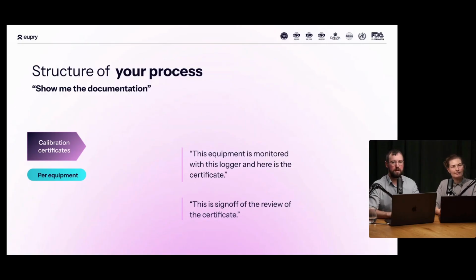We got a question here: if we calibrate the high point at 10 degrees, the materials inside the unit are exposed to temperature out of operating range, is that okay? No, it is not okay. But for excursions specifically, I have yet to see someone storing something in a fridge that did not from time to time experience excursions. The point is, if your target range is 2 to 8 degrees and you have an excursion up to 10 degrees, or sometimes higher, you'd also need to extend your calibration range. You need to show with confidence that the excursion was not more than 10 degrees, and how can you do that if you haven't calibrated it? It's never okay to expose it to more, but when you do have a temperature excursion, you can calculate the mean kinetic temperature to verify it.